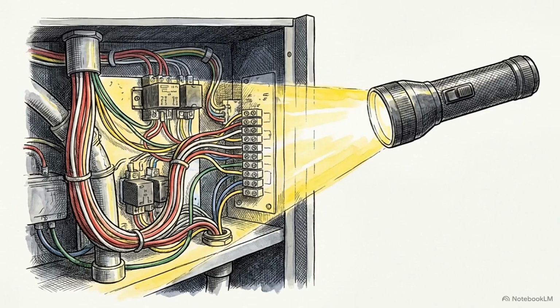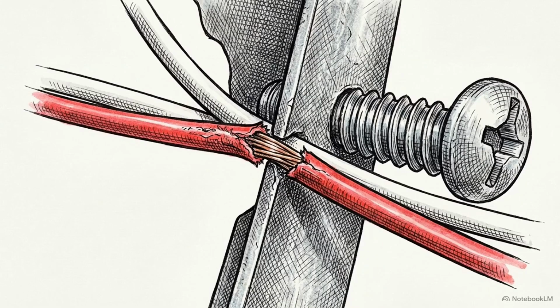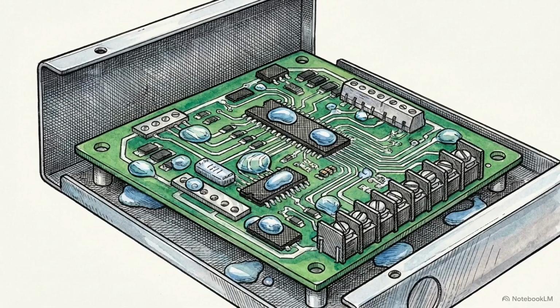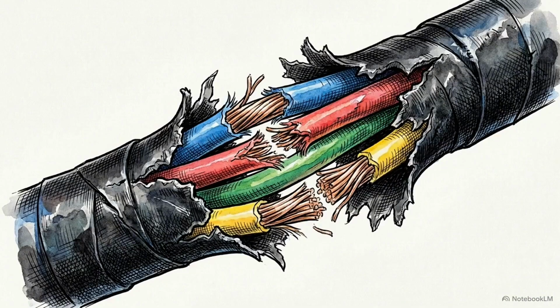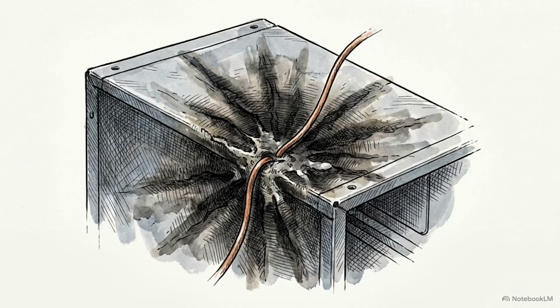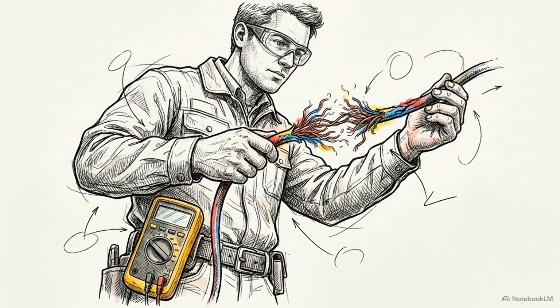With the power secured, perform a close visual sweep of the cabinet. Look for pinched wires trapped behind access panels or thermostat wire insulation that has rubbed raw against a vibrating piece of sheet metal. Check for environmental issues: moisture pooling inside electrical enclosures, loose wire strands touching a grounded chassis, or outdoor wiring chewed by rodents will often stand out clearly. A dead short severe enough to blow a fuse instantly almost always leaves visible evidence. Taking 60 seconds to sweep the cabinet often solves the problem before you ever connect a meter lead.